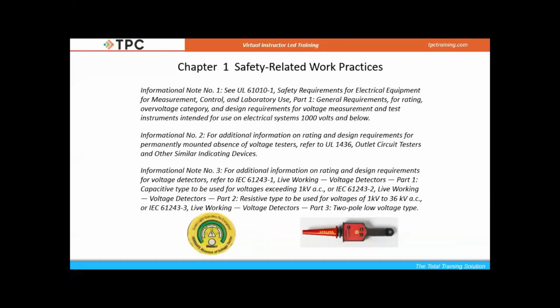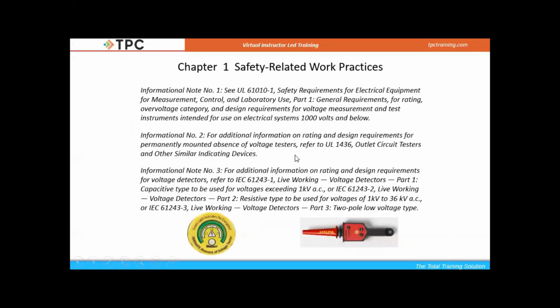But here's what my father told me when I was very young. Bob, nobody else is going to take care of you, so you better take care of yourself. And so I'm not sure I want to put all of my trust in those green lights, but people do all the time. And then to the right, we do have a non-contact tester, and this would be used for over 1,000 volts. You can see that it would be mounted at the end of a hot stick. Those I've used for a long time. And as long as we test them before and after, we should be fine by using these non-contact testers.